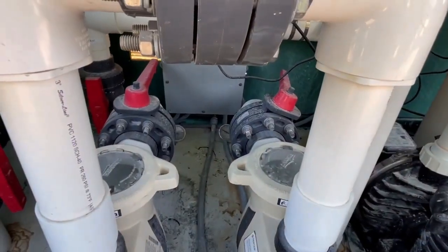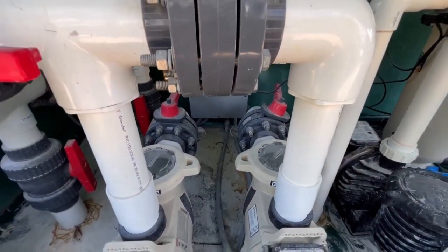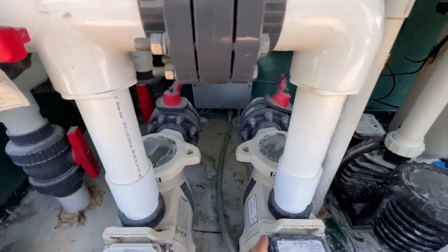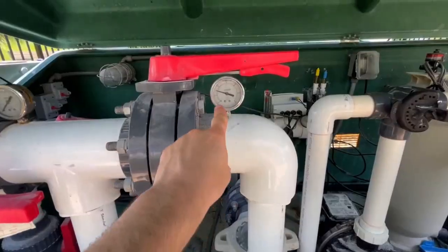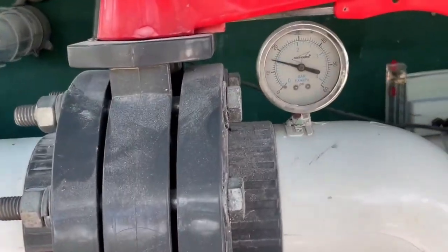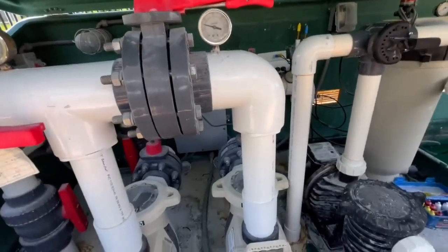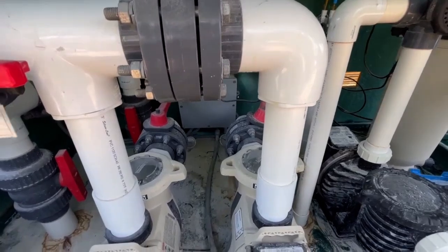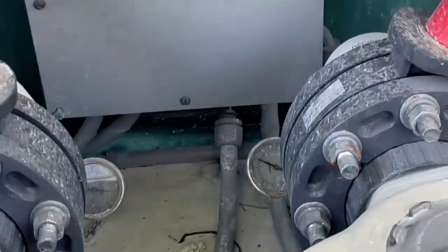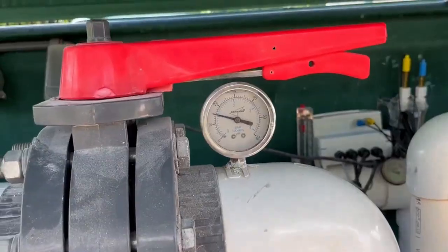What we want to look for, to make sure everything's running smoothly, that's suction side. What is the number on the return side? We're looking at about 15. That's fine. You don't want a difference of more than 10. The critical thing to note is the difference, right? If that says 15 and this said like 40, that means we have a serious problem.